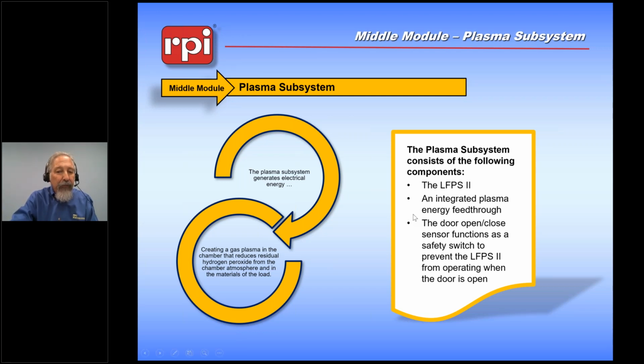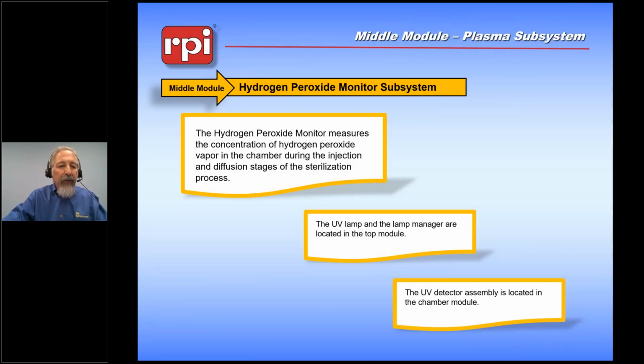The way that's done is through a power supply. There is also a feed through that allows the electricity to come into the chamber and not directly contact the chamber walls. And there is also a separate door sensor to be sure that you cannot turn this system on when the door is actually opened. The middle module also contains the hydrogen peroxide system, as we talked about earlier. The hydrogen peroxide monitor uses a UV light to measure the transmittance through whatever material is in the chamber. The UV detector is located on the bottom. The light is located at the top.